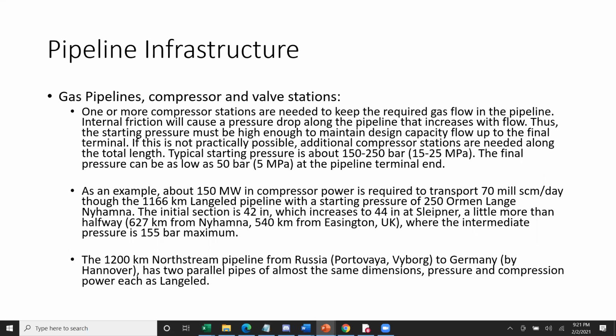I'll talk a little bit about gas pipelines, compressor, and valve stations. One or more compressor stations are needed to keep the required gas flow in the pipeline. Internal friction will cause a pressure drop along the pipeline that increases with flow. Thus, starting pressure must be high enough to maintain a design capacity flow up to the final terminal. If this is not practically possible, additional compressor stations are needed along the total length. Typical starting pressure is about 150 to 250 bar. The final pressure can be as low as 50 bar at the pipeline terminal end.